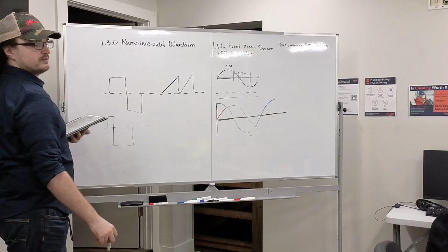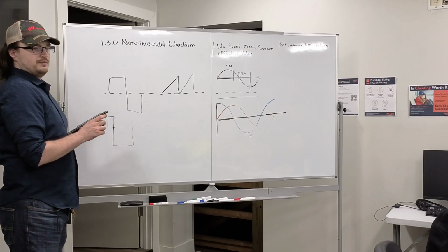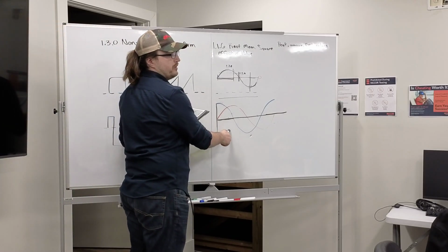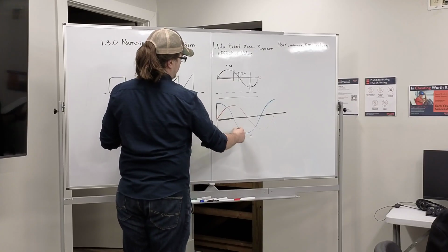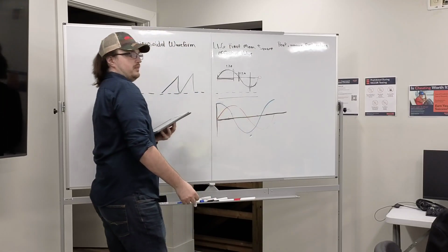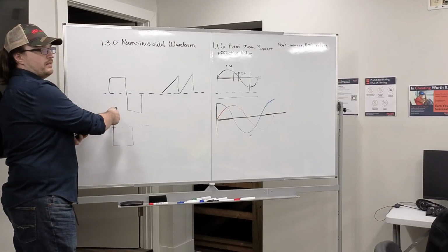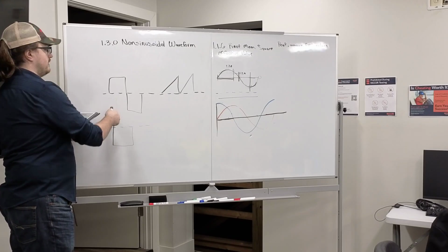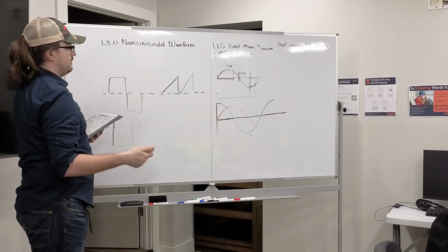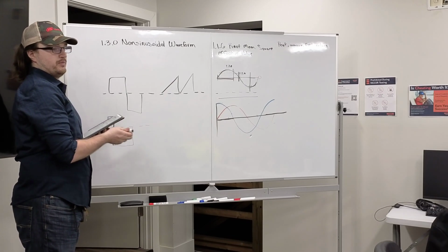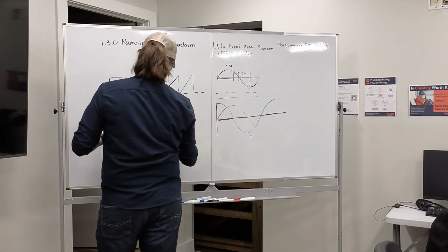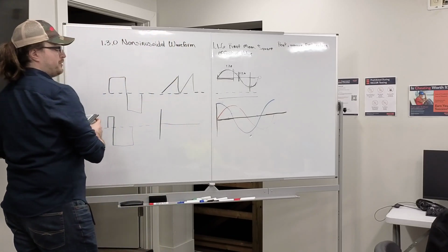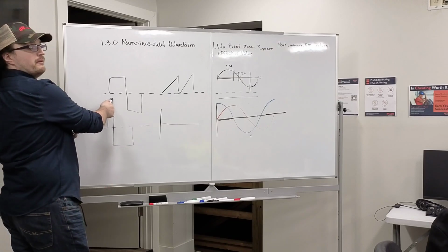So why do they look like this? The question was. Because they're not circular. Sine waves are produced by a generator which moves in a circle, so it has a smooth circular motion creating a sine wave. These are probably created artificially by digital devices. For example, a variable phase drive that controls the motor, if it's a really cheap one, it'll look like that.